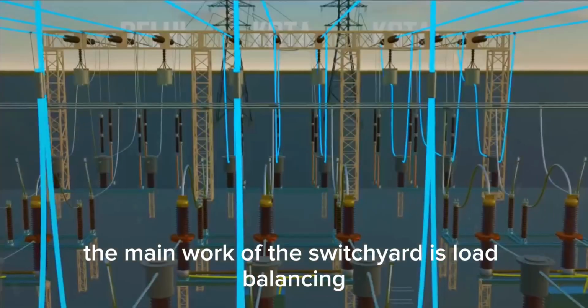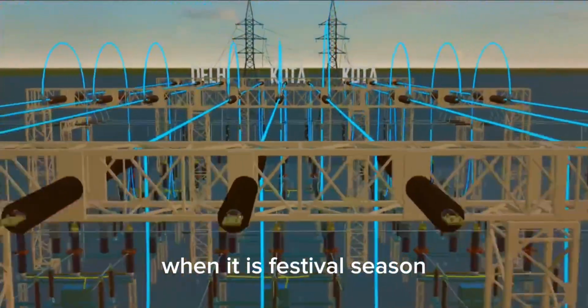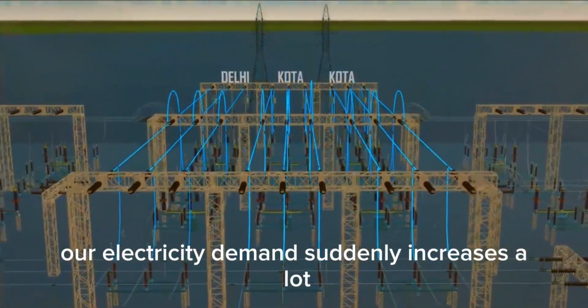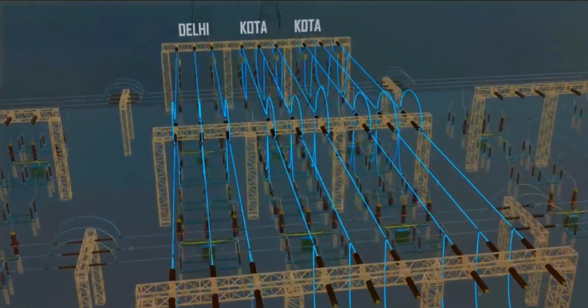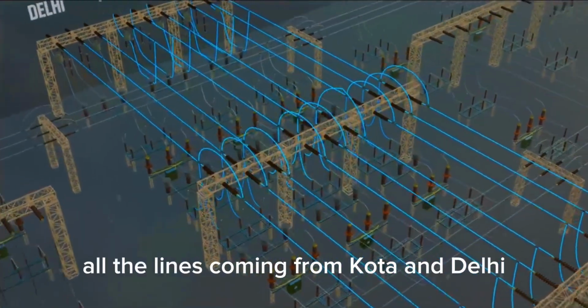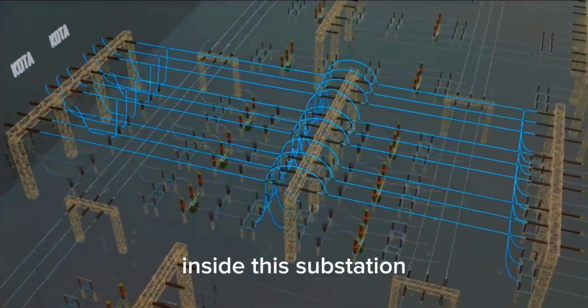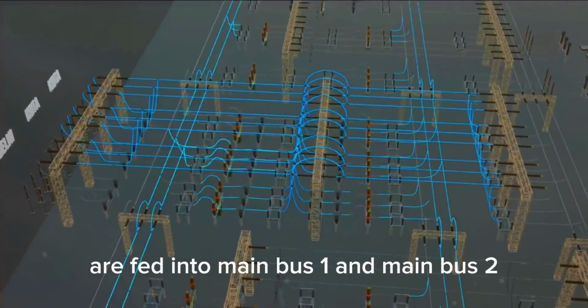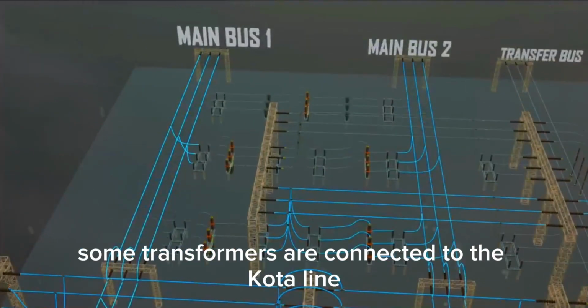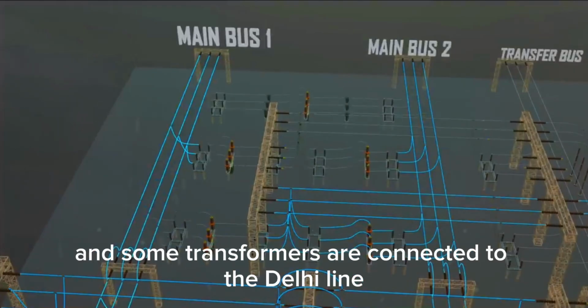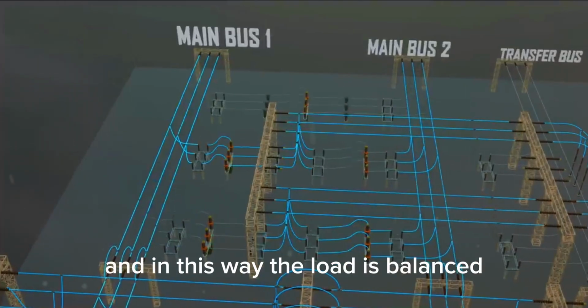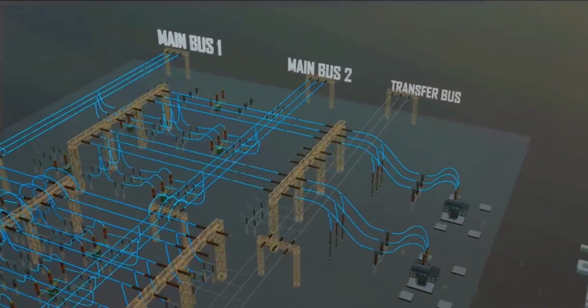The main work of the switchyard is load balancing. When it is festival season, our electricity demand suddenly increases a lot. So in such a condition, all the lines coming from Kota and Delhi inside this substation are fed into main bus 1 and main bus 2. Now when both the buses are charged, some transformers are connected to the Kota line and some transformers are connected to the Delhi line, and in this way the load is balanced.